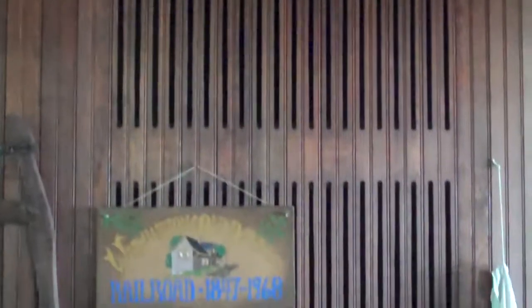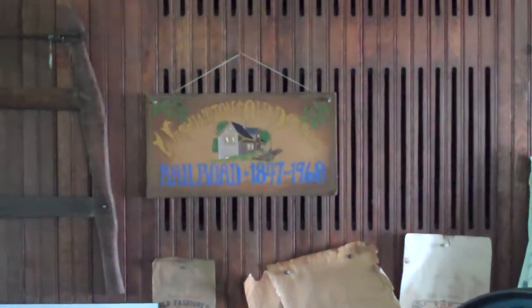If you look carefully in the wood system here, you can see there's some ventilation that allows some of the heat to come out from behind the wall where the pipes go. More windows — single pane. This is a historical site, so the chances of us changing these windows out are going to be almost nil. We have a lot of paneling here against the walls, which sometimes causes problems. We don't know what's behind the walls — we may have some leakage there.